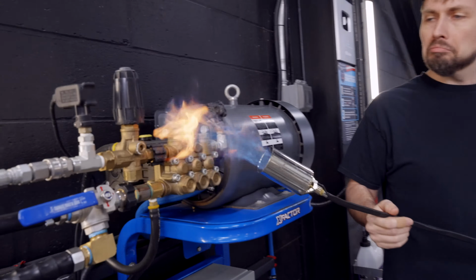Using a small knife seems to help. This is like a little insert piece here that holds the ceramic stable, and you've got a couple small seals inside of this. We'll throw some Loctite back on these too, because you don't want the nuts loosening up inside your pump while it's running. All right, sleeve number 2.